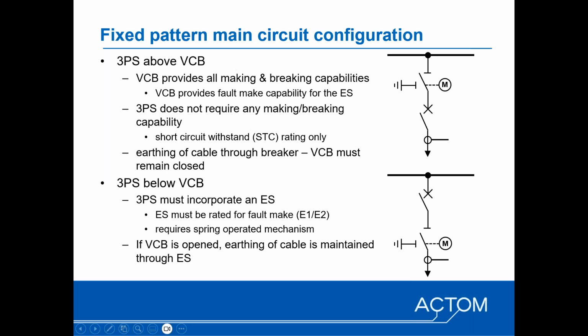What's important to note is that earthing of the cable is done via the circuit breaker. In the example underneath, we've got a reversal of the order, where the circuit breaker is above the 3-position disconnector. In terms of fit, form, and function, these are equivalent.